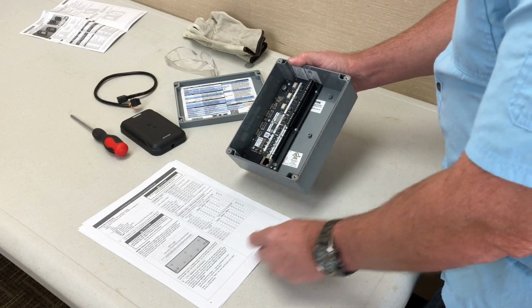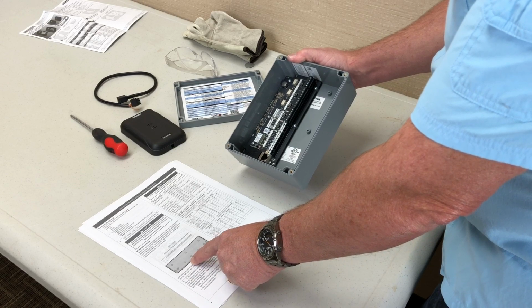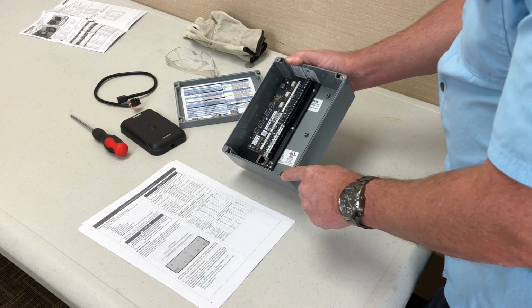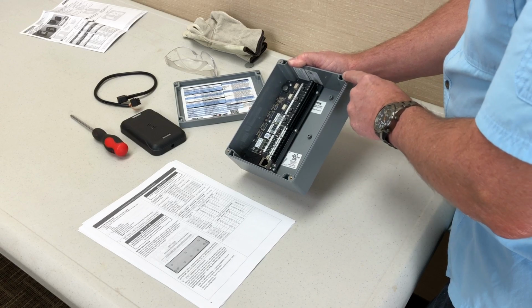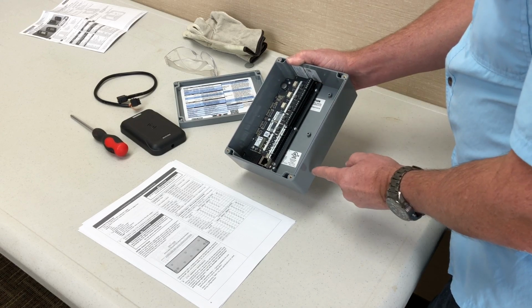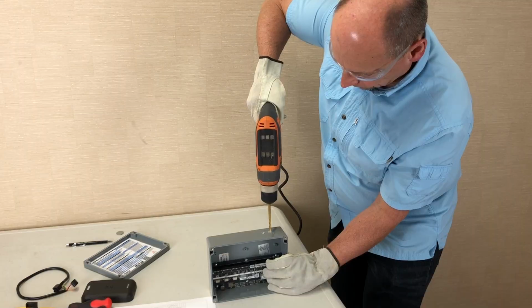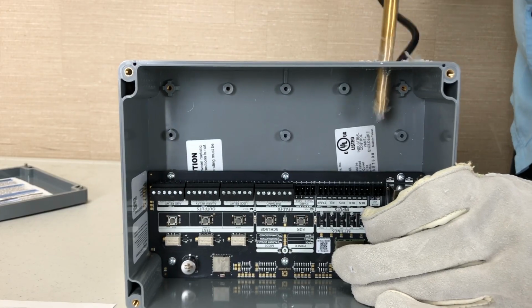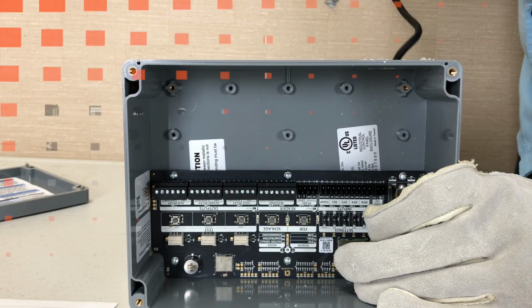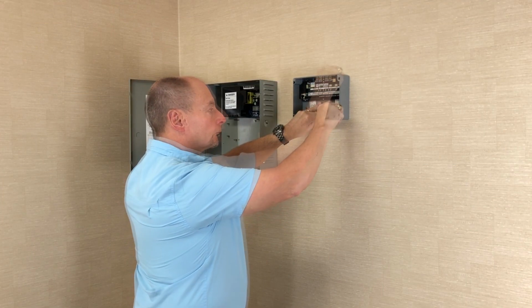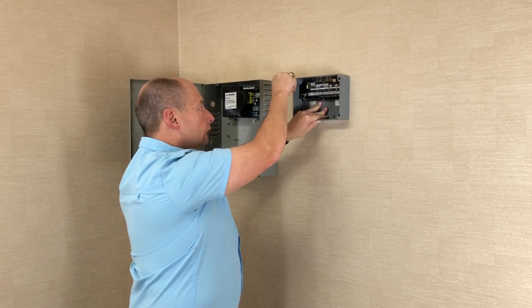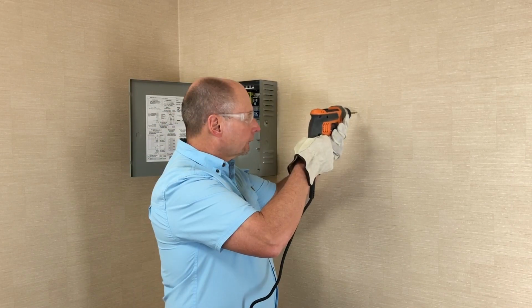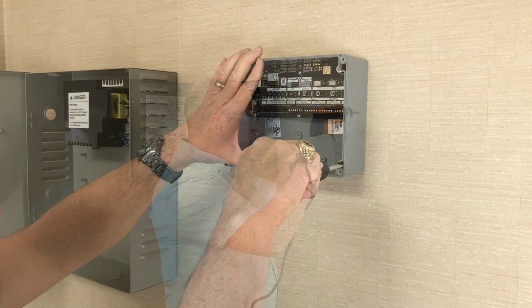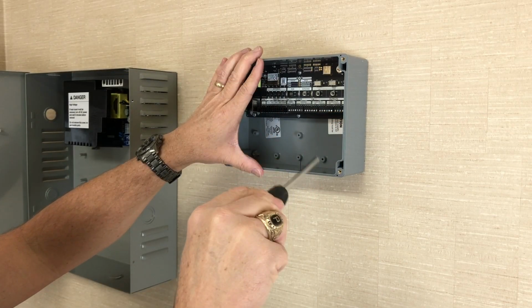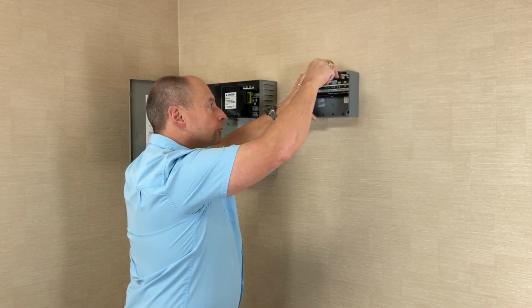Determine where wiring will enter the CTE enclosure. Holes can be drilled only in the area beneath the circuit board on the bottom, back, or sides. Drill a hole for the wires, using caution not to contact any electrical components. Mark and drill 4 holes with the 9/32 inch bit that correspond to the 4 CTE mounting holes, as shown. Then secure the CTE with appropriate fasteners for your wall type.